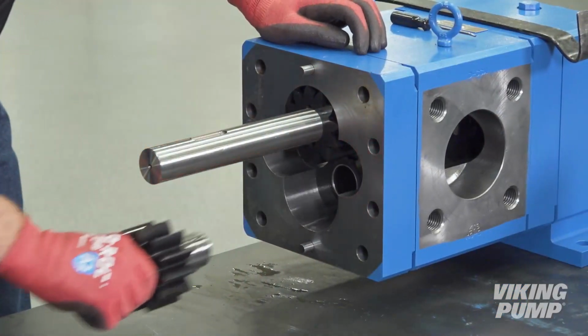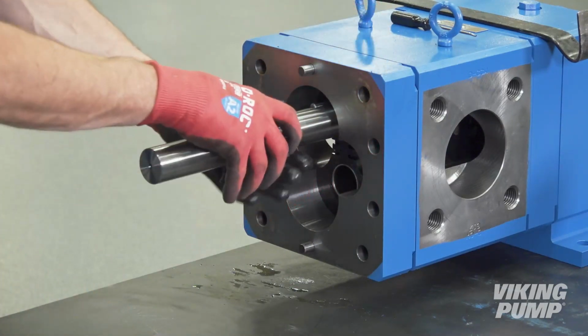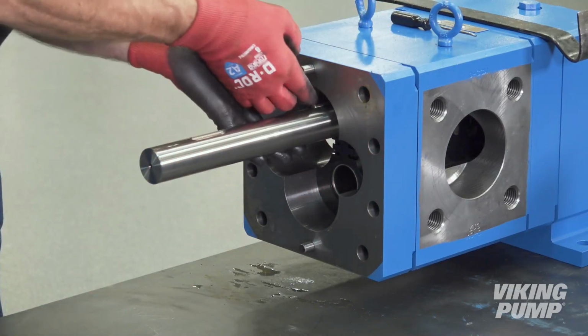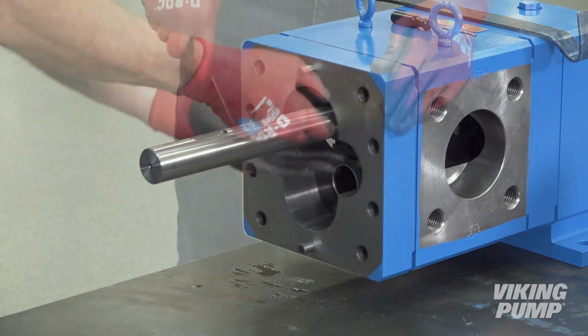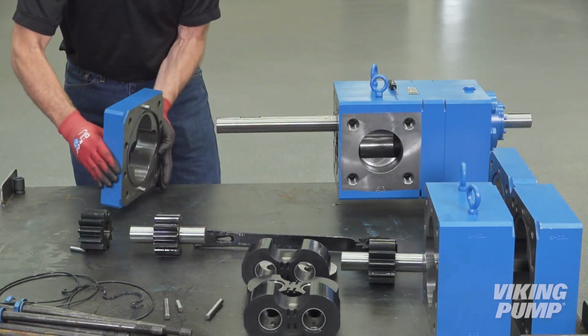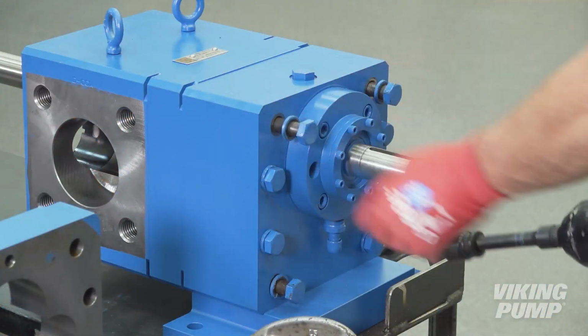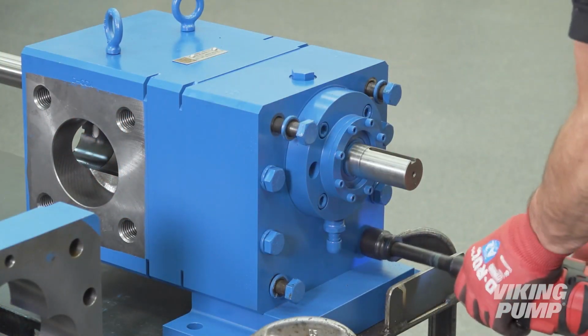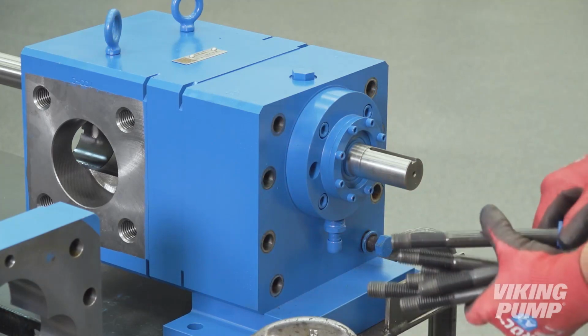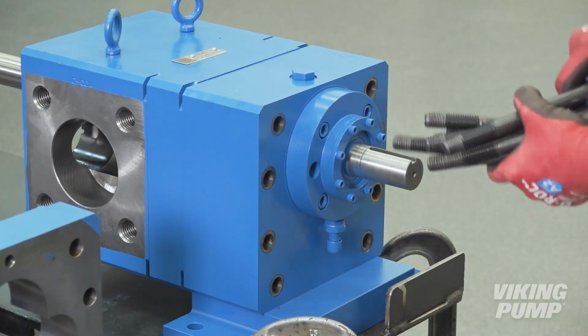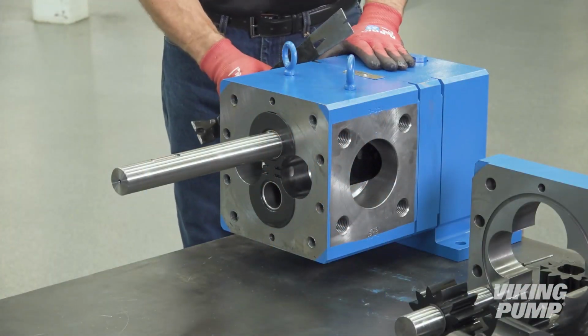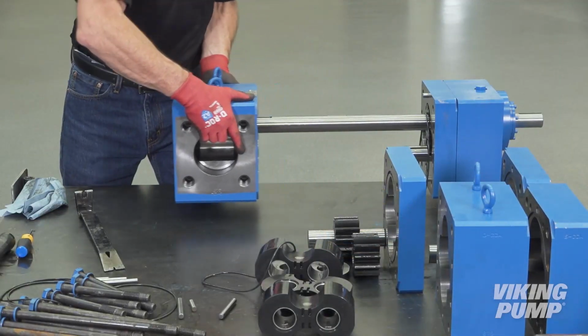Remove and discard the driven gear and shaft, the driver gear, and drive pin. Next, remove and discard the casing and alignment pins. Use a 15/16 inch socket to loosen and remove the cap screws on the bracket end of the pump. Discard these cap screws. Next, remove the ported separation plate. Set this aside for reassembly.